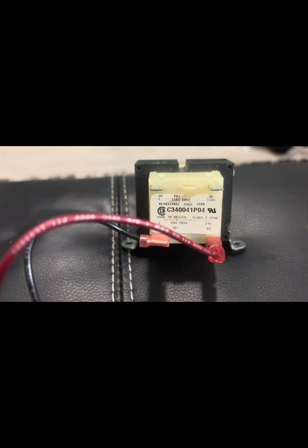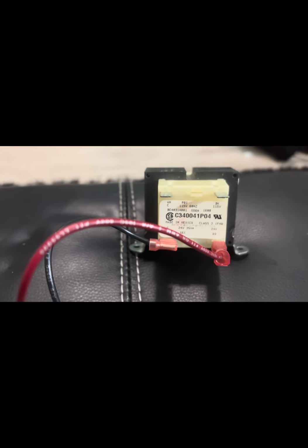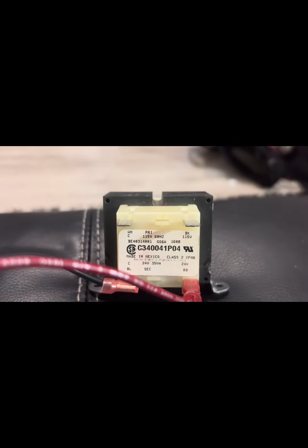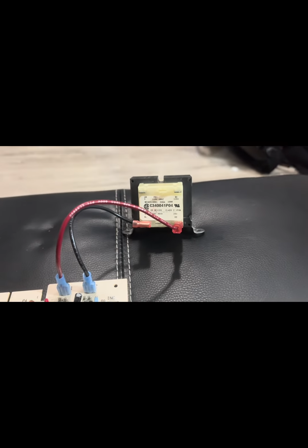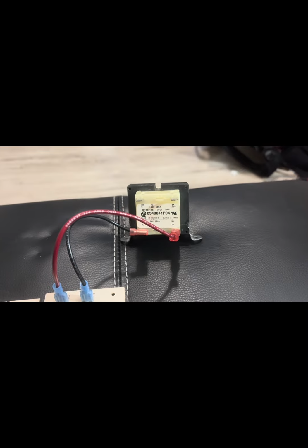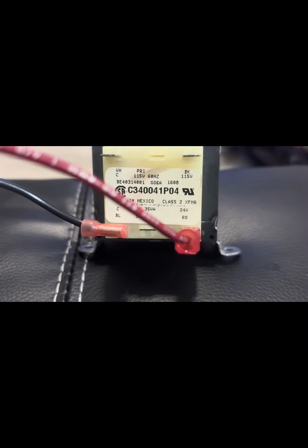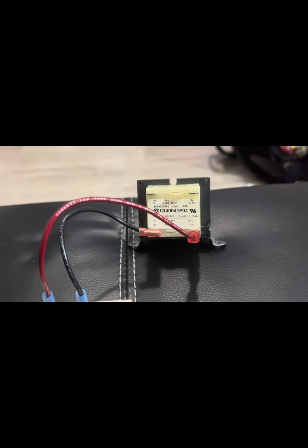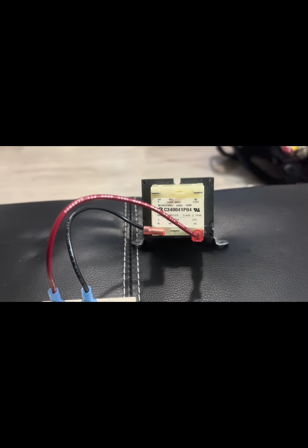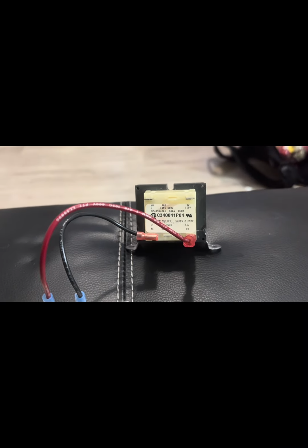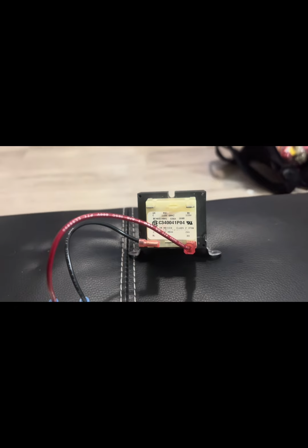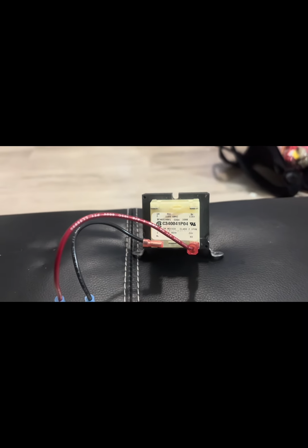Now for your transformer, this converts that high voltage on your primary side to the 24 volts on your secondary side. This powers all low voltage components. Your low side, you see that 24 volts for your red, common for your black. So for this one, we're going to be using the red for our hot and the black for our common. The transformer is the source of the 24 volts components. It powers all low voltage components.